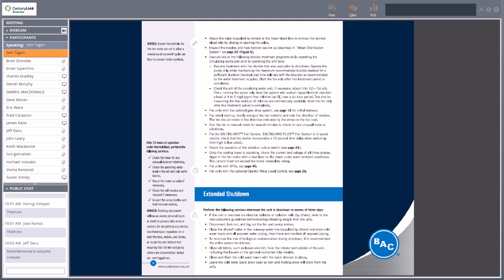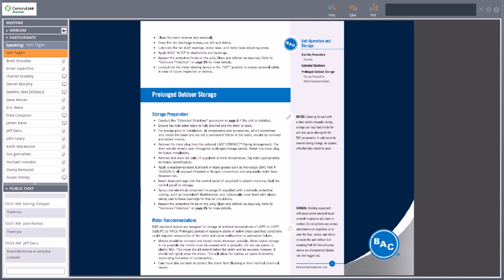So, again, jumping back on the page, extended shutdown: if you're going to drain the tower, put it up for the winter and leave it, there are step-by-step instructions, and again, it starts with cleaning, talks about removing the dirt, and making sure that you grease and lubricate everything for the winter. It talks about draining the cooling tower, leaving the drain valve open so that you don't have any freeze issues, and then it talks about how to store the motor. It recommends removing the motor and storing it inside wherever possible. I'll be honest with you, I'm not sure I've ever seen anyone do that.